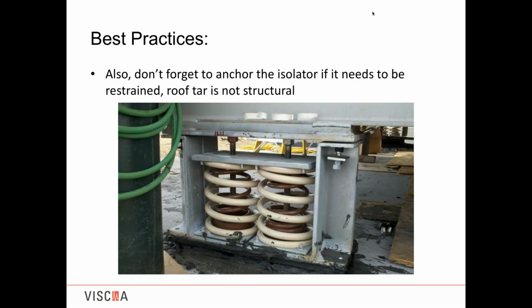And here, for outdoor applications, wind and seismic applications, you have to anchor the isolator to the building or weld it to building structure to be restrained. In this case, trying to use roof tar as a structural adhesive in shear does not work. And if you look closely, you'll also see this top plate is touching the lower housing, so this was not adjusted properly. So we'd get this picture to the manufacturer.